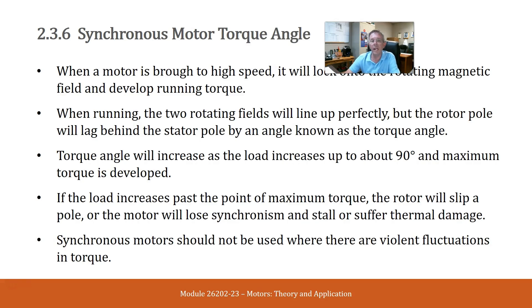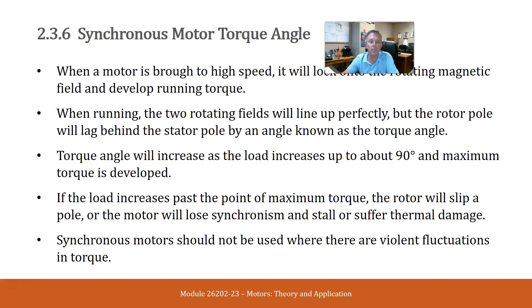Synchronous motor torque angle. When a motor is brought to high speed, it will lock onto the rotating magnetic field and develop running torque. When running, the two rotating fields will line up perfectly, but the rotor pole will lag behind the stator pole by the angle known as the torque angle. Torque angle will increase as the load increases by up to about 90 degrees, at which point maximum torque is developed. If the load increases past the point of maximum torque, the rotor will slip a pole, or the motor will lose synchronism and stall or suffer thermal damage. Synchronous motors should not be used when there are violent fluctuations in torque.